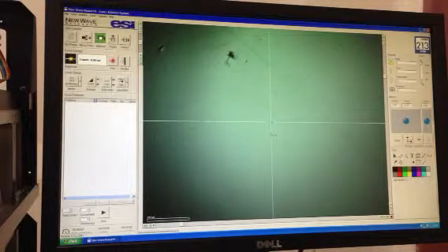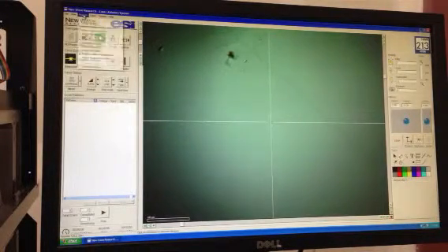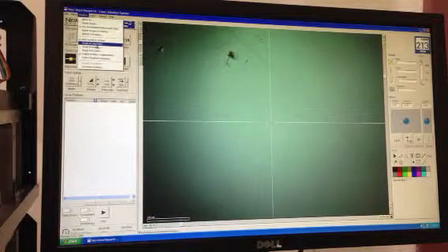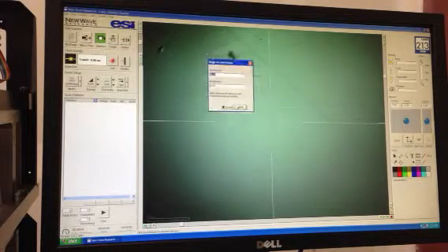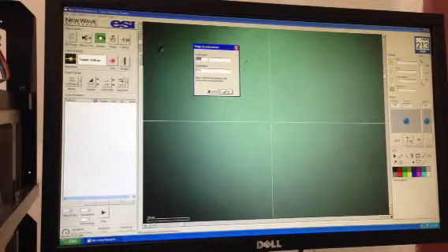There's a few things we want to check or set before we start this characterization test. The first of which is stage accelerations. Stage accelerations are hidden in the position pull-down menu. If you hold the control key when you hit the position pull-down selection, the stage acceleration selection is available. So you hit stage acceleration and this small GUI comes up. For Truline stuff, all the characterization work has been done at acceleration of 5,000 and deceleration of 2,000. So go ahead and set or verify that these are correct and hit OK.